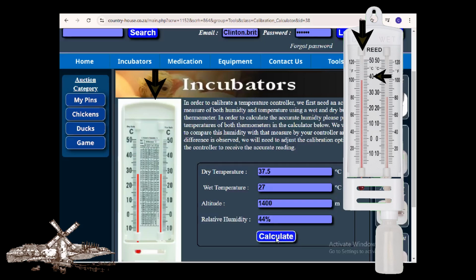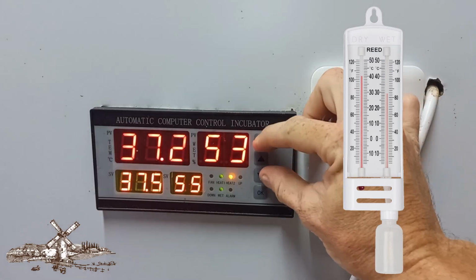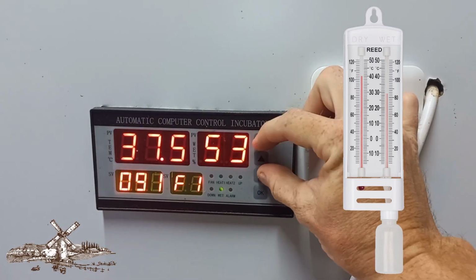So by default, my controller measures 37.5. And so what I need to do is tell the controller that from now on, because of error, I need it to add 2.5 degrees onto every temperature measurement before it displays a temperature measurement on the screen for me to see, or that it uses in order to actually turn heaters on and off to adjust temperature. Now, with an XM18 controller, the value we need to change is in fact the F5 value. To get to the F5 value, all we have to do is push the set key, hold it in, and then tap just the down key. And you will see F1 appear in the bottom right hand corner.